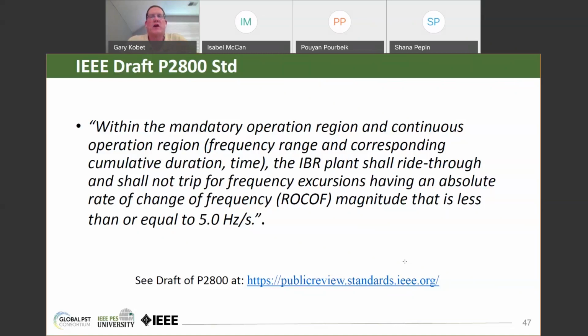entity decided that they would set their limit for inverter-based penetration. Their limit is that the rate of change of frequency can't be higher than 3 hertz per second in their system, is what I remember. And I will recommend a paper by the vice chair of this task force that developed this paper. Kevin Jones and some colleagues wrote a paper called "The Need for Faster Under-Frequency Load Shedding," and I highly recommend it. It provides a little more detail on this subject.